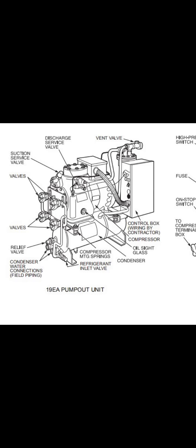So remember that when you put the reverse cycle, the discharge hot gas is going to the condenser, taking suction from the evaporator. What you have to remember is to open the condenser water line, two valves there. You open the water flow valve. But I say this should not be condenser water; we recommend the chill water line. Chill water is available in the plant room.